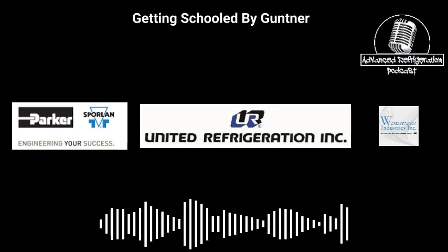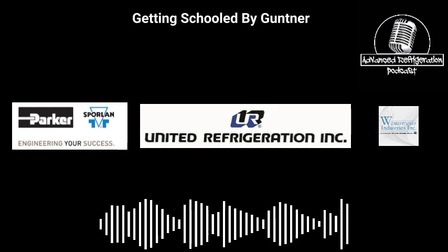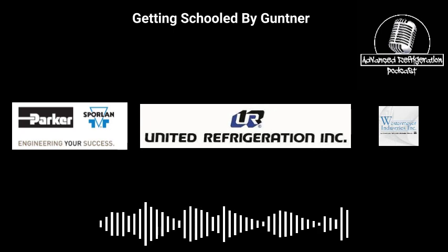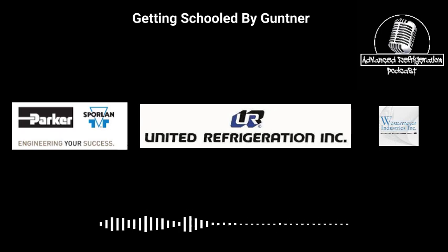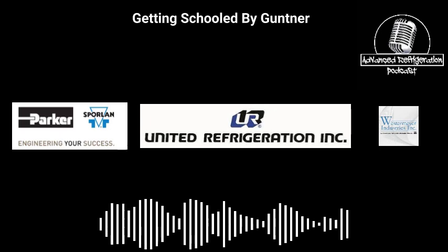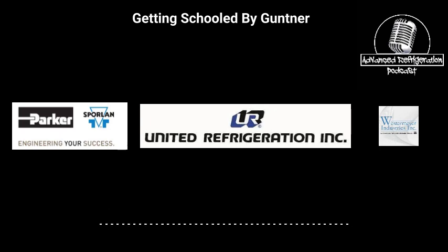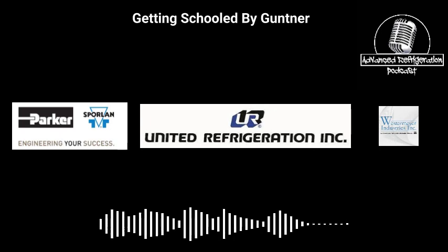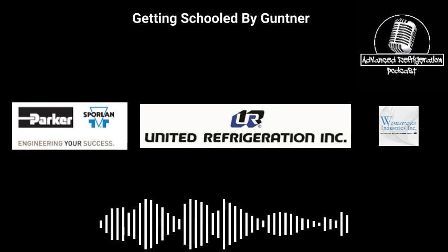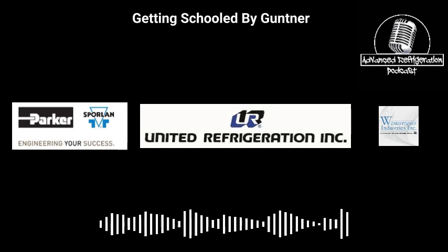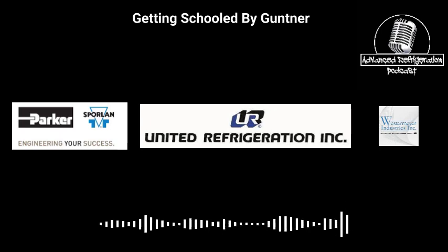So now getting into the adiabatic side. Right here we have our GHM controller. On the left, we have our GMM, and on the right, we have our GHM. GMM stands for Guntner Motor Management. GHM stands for Guntner Hydro Management. The GMM will control the fans and ramp them up and down. The GHM looks at the ambient temperature and the ambient humidity, and the GMM tells it what the fan speed is, and it'll determine how much water to put across the fans.